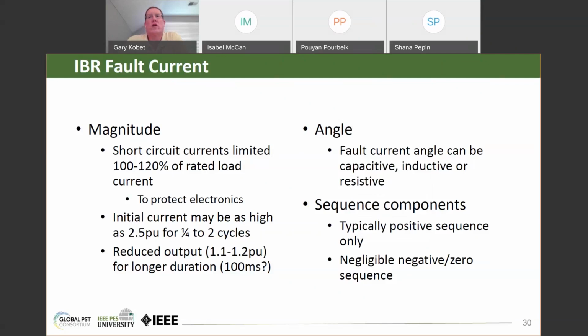So there may not be as much difference between load current and fault current. And the fault current angles are essentially undefined, so we're not sure what we're going to get with those. And the other piece is the sequence components. This is an issue for unbalanced faults, but IBR typically produce only positive sequence and negligible negative and zero.